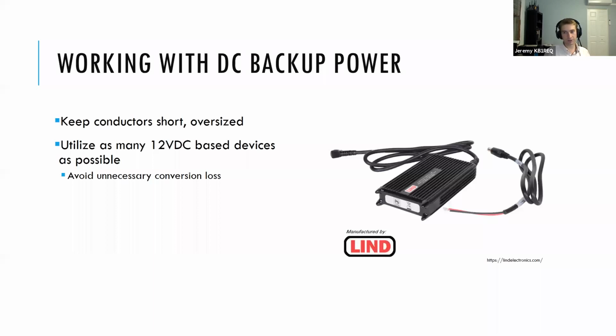You're going to have some inefficiency in the conversion up, and you're going to have some inefficiency back in that conversion down. So if you can keep things at 12 volts, keep them at DC, that's going to be a more efficient backup solution. Of course, the downside is you're at DC, so your copper loss is a lot higher. So you've got to make sure you're keeping your conductors short and oversize them for voltage drop if they are a little bit longer. But just something to keep in mind, if your backup power solution is DC, make sure you're doing as much as you can at DC in order to make the most of it.